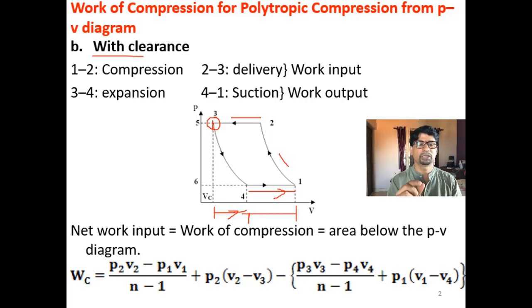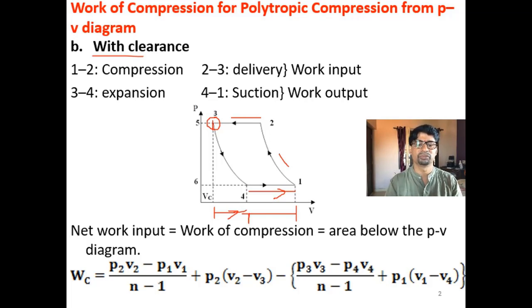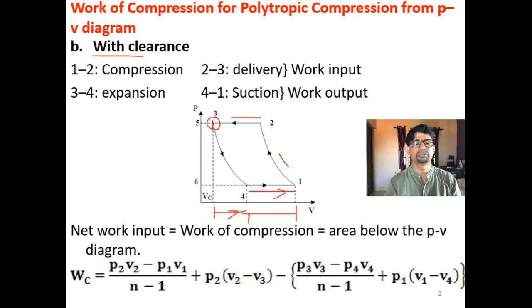Initially, the small amount of compressed air left in the clearance volume expands from 3 to 4. The actual suction begins from 4 to 1. Now, the net work input — that is, the work of compression — is nothing but the area under the PV diagram.